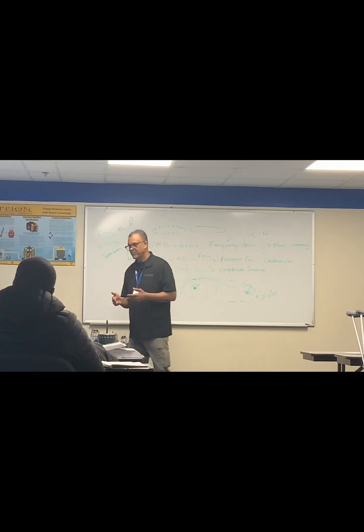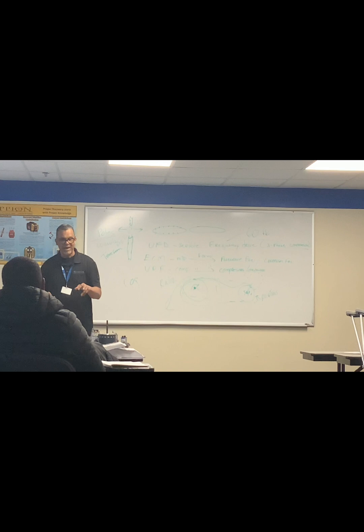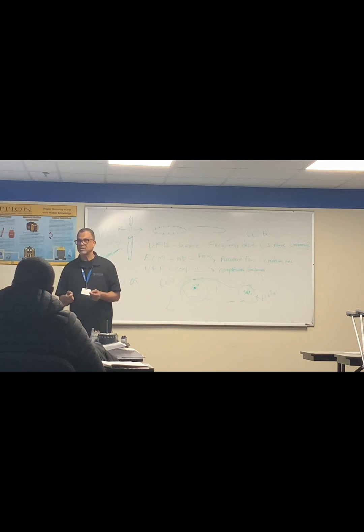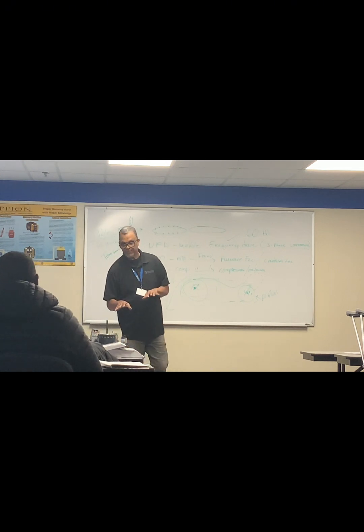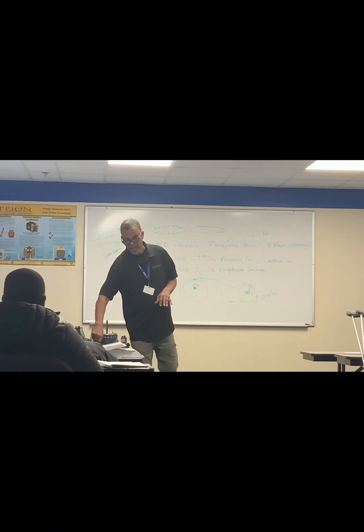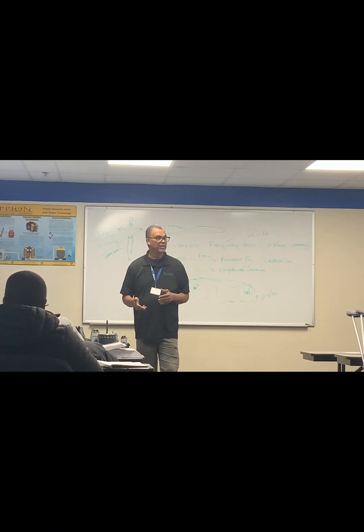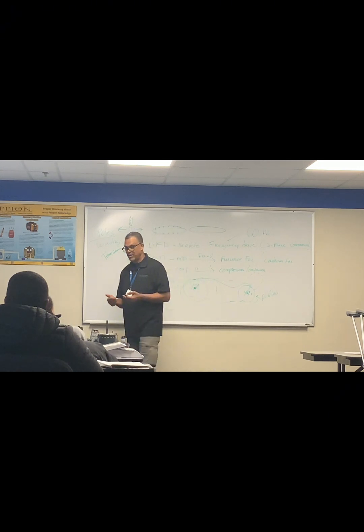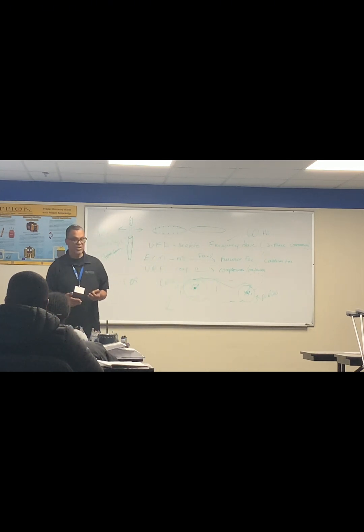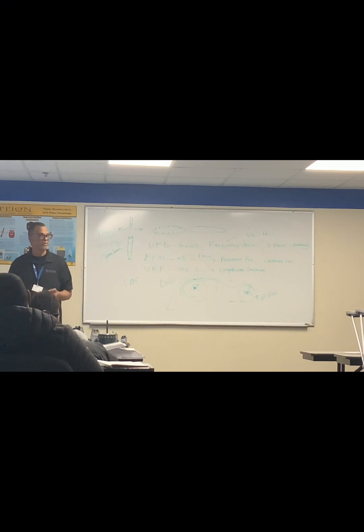So there's another video we're looking at another time, how to test an ECM motor, because it's not the same thing. You have DC coming out on the lower part of the unit, DC, and then AC feeding. So if you have the DC, you know you have the AC. And since you have digital boards, it's always controlling some function of the motor. So you don't know if the card has failed or the motor has failed, and there are ways we can test it.